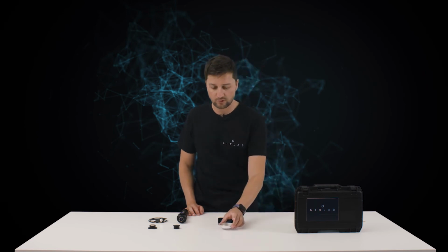Ambient light can interfere with the measurement. It is not recommended to make analysis with the device pointing upwards. In order to measure small samples, it is recommended to use an aluminum cup. Aluminum has a neutral effect on the spectrum. Substances with a surface bigger than the device detector can be analyzed with the device in any position.